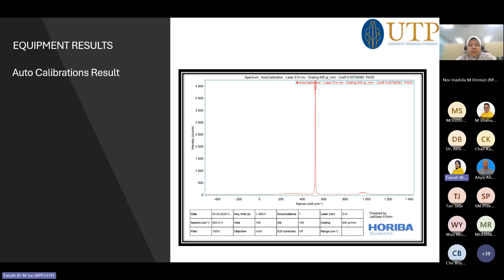Number three, from this graph, we can see the coefficient obtained, 0.00758, is within the acceptable tolerance and the system status is marked as pass. From the graph, we can confirm that it is accurately calibrated before acquiring graphene or other sample spectra. The sharp silicon peak observed at 520.8 validates successful auto calibration. So after calibration, we get auto calibration pass. So I can proceed to the next sample or other samples.